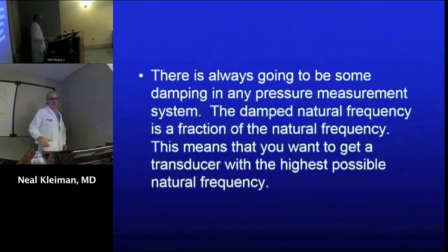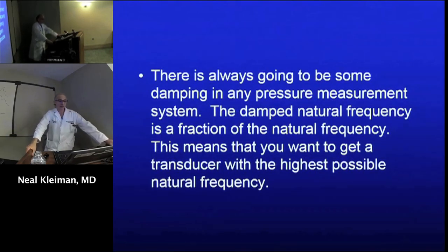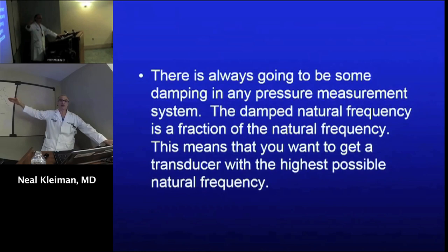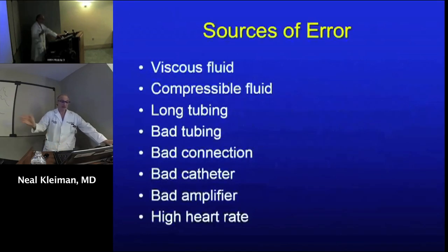So we've gone through that. You're always going to have some damping in a transducer, in any pressure measurement system. The damped natural frequency is a fraction of the natural frequency. This means you want to get the transducer with the highest natural frequency possible, so you can reproduce those harmonics, and the farther you are from the fundamental or natural frequency, the less likely you are to have that underdamped situation where you're amplifying the small harmonics. So two good reasons to have higher natural frequency transducers.